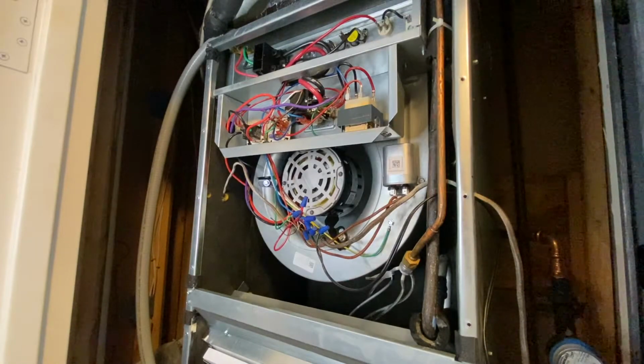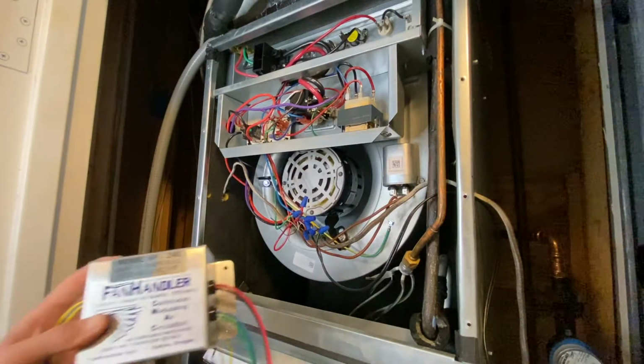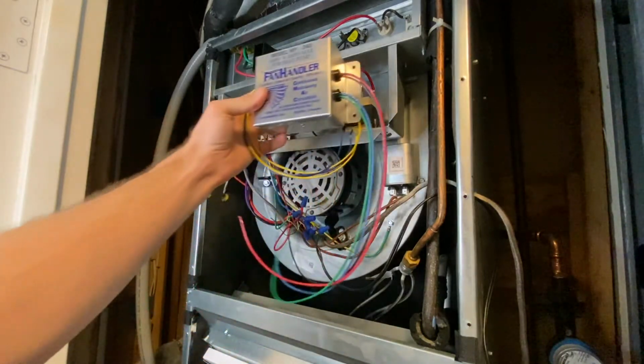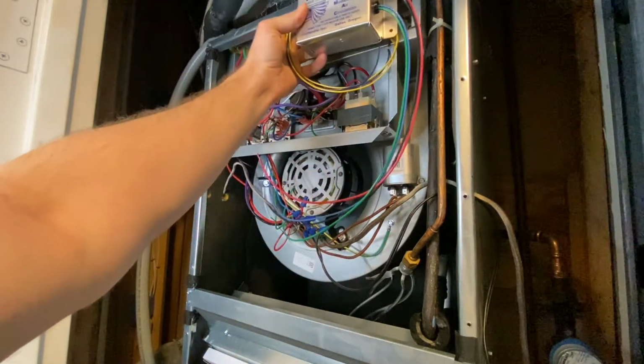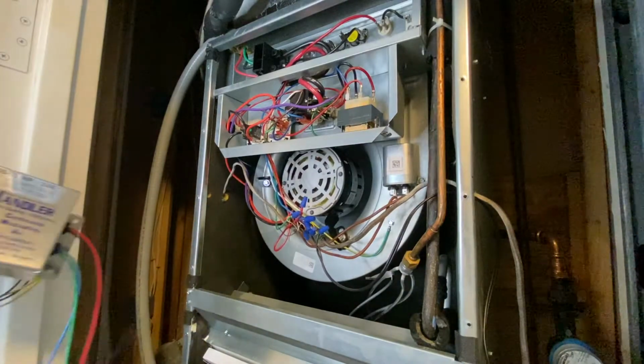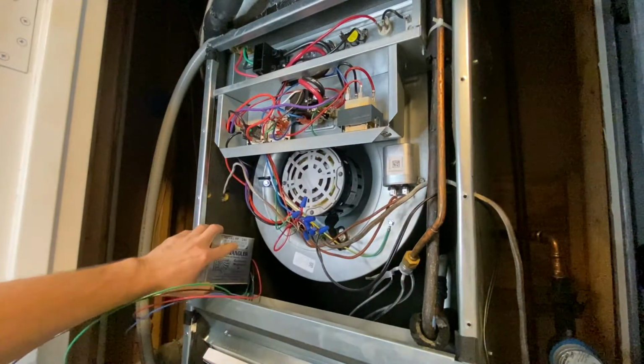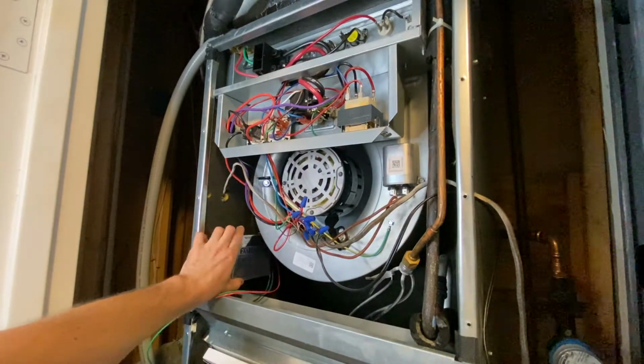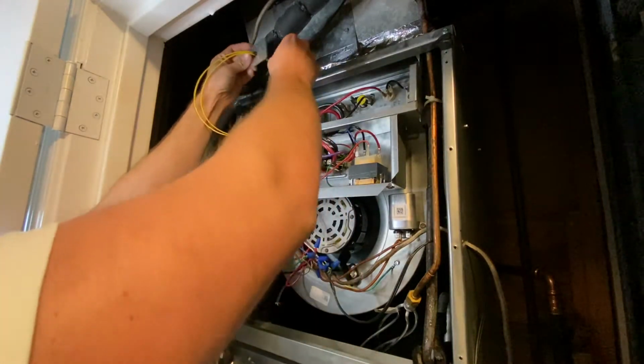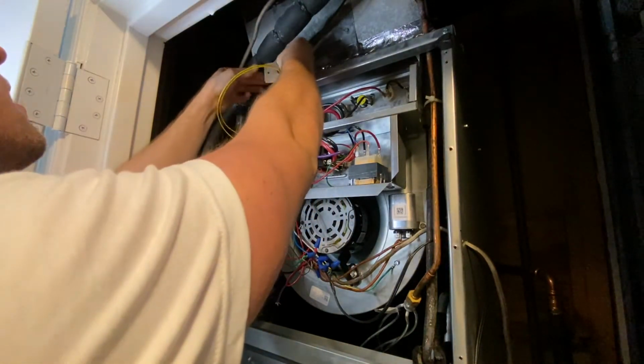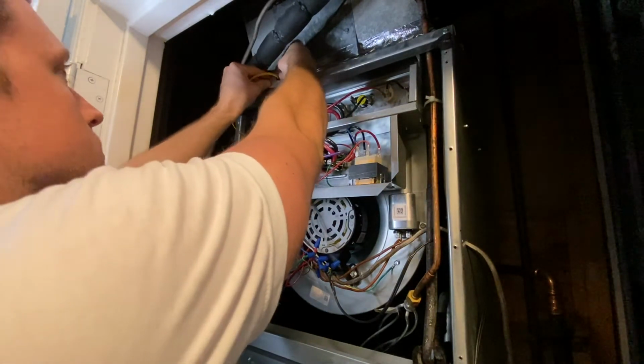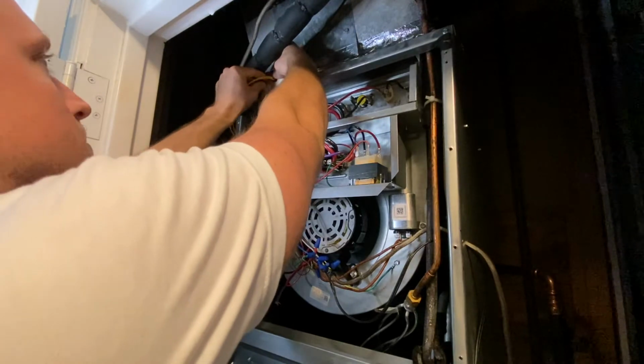The first thing we should do is figure out where we're going to mount the fan handler system. There's really no room up here, so I'm going to mount it right on the side here, and install the two temperature sensors up at the beginning of the supply duct. I've poked some holes through this ductwork, and I'm just going to feed them through.